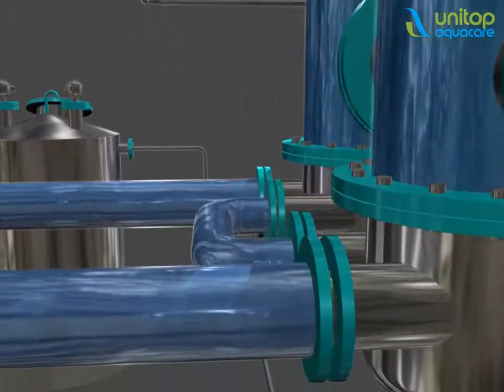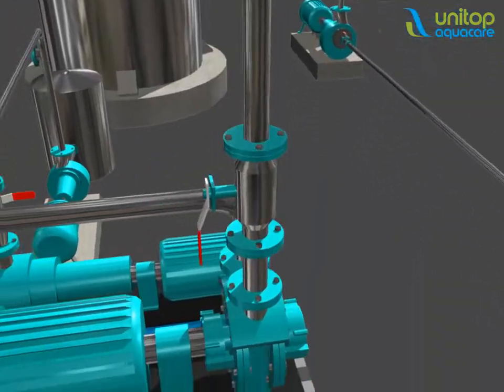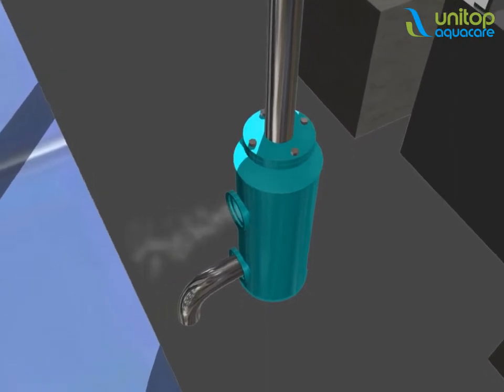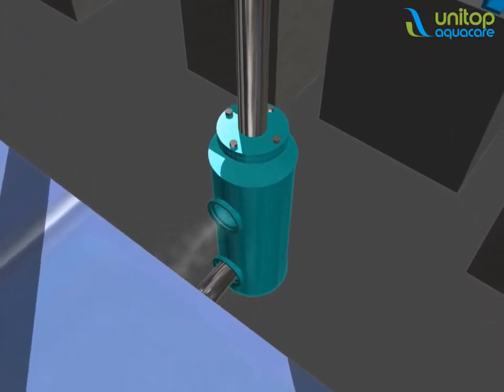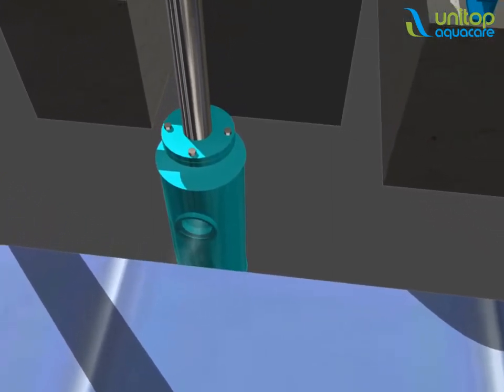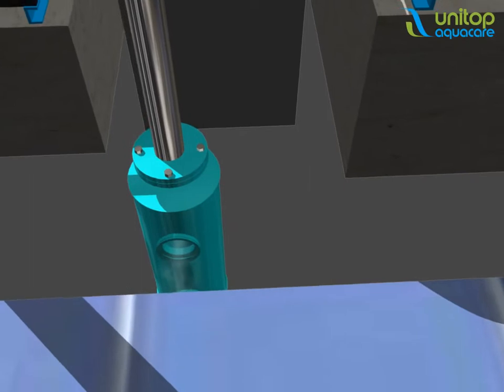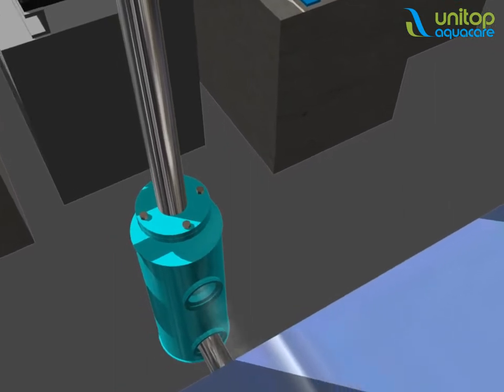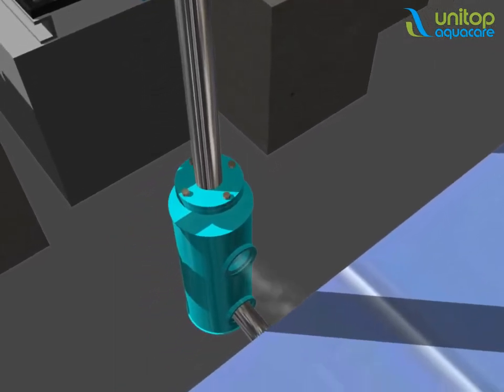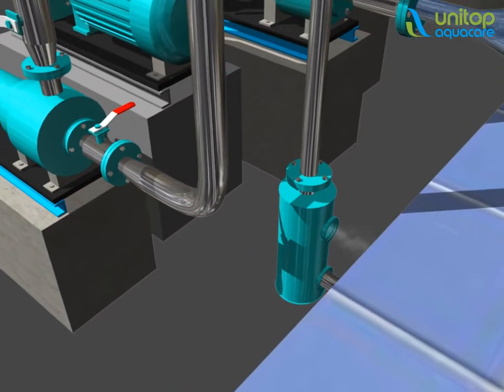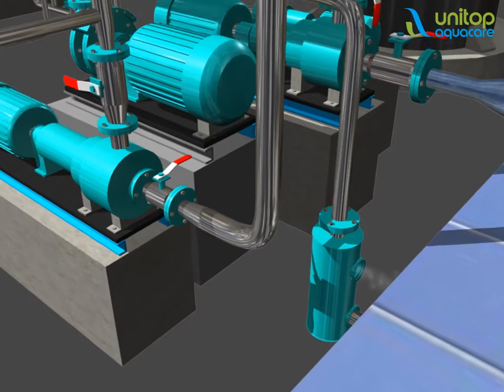Importance of applying vacuum in the system: Air removal from the system is decisive for efficient working of the evaporator. The air has low heat transfer coefficient and can drastically affect the evaporation rate. Also, leakage of air in the system results in lower vacuum, which in turn results in lower temperature difference between each effect, resulting in a drop in capacity. This vacuum is produced by a water ring vacuum pump connected to the condenser.